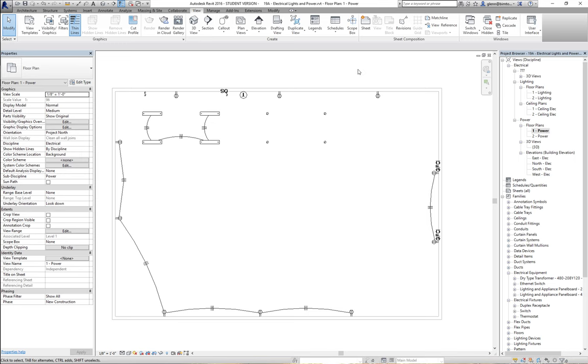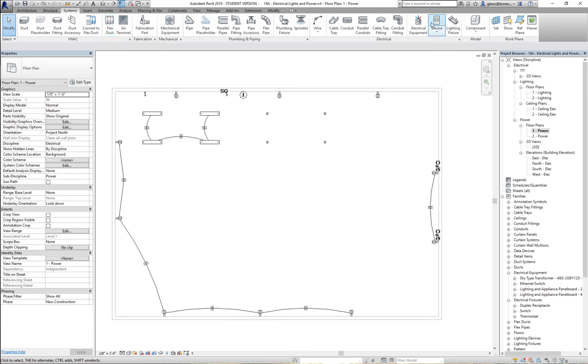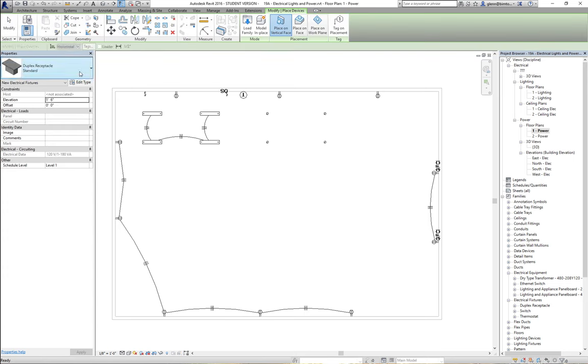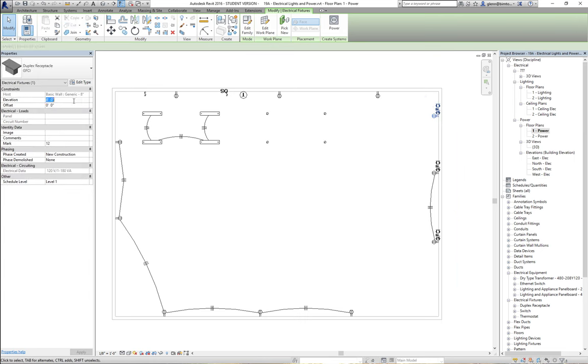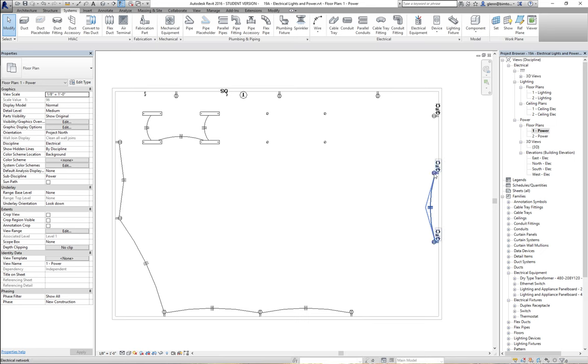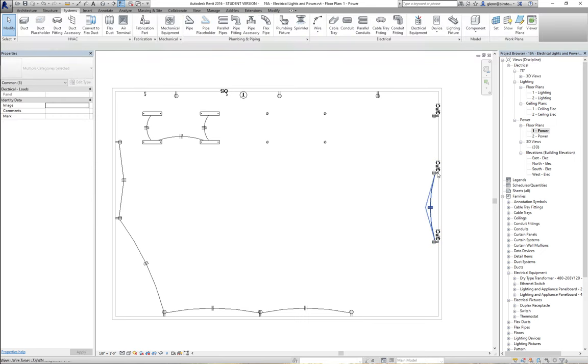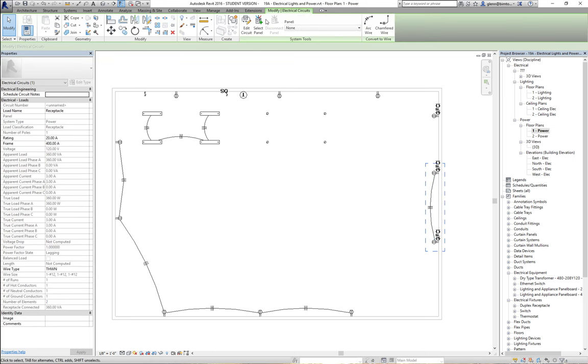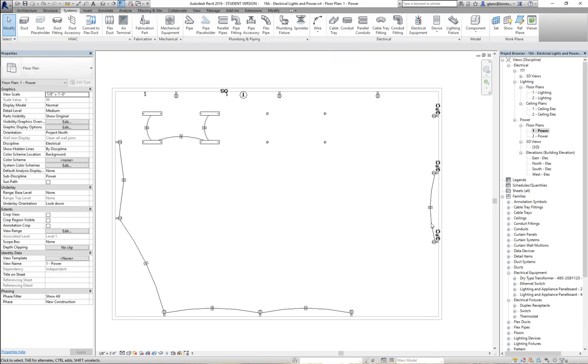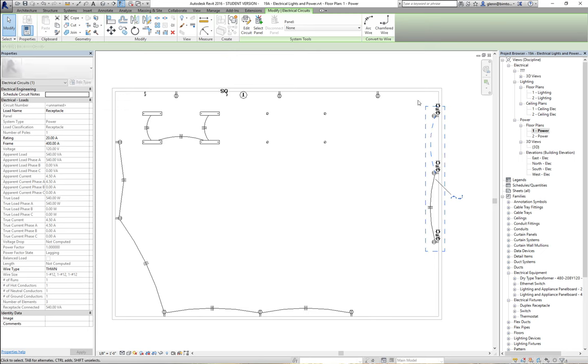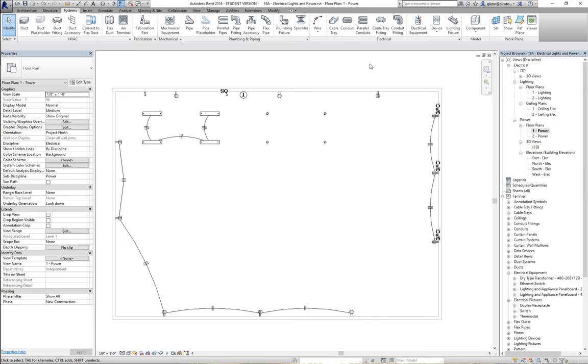We can tie those together. I could take these other outlets, create a system out of them, edit the circuit, add this one, finish that circuit, wire them, and have another circuit that starts to tie them together. In a lot of buildings, this will be P101, this will be P102, and they'll distinguish the power circuits versus the lighting circuits. Power tends to work out pretty well. If you need to put an outlet in an unusual location, you can come back, go to systems device, put another GFCI outlet in a countertop or special height location at like three foot six, then edit the circuit and add that to it.